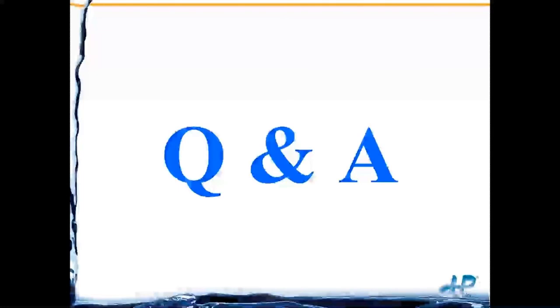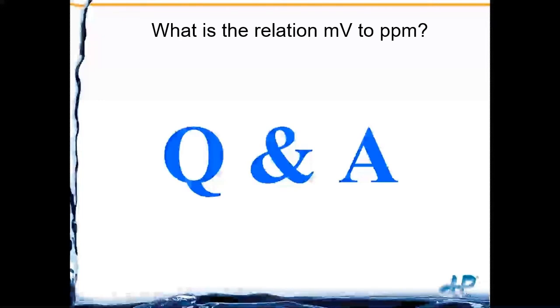Process analyzers is an always-changing world. If I don't know an answer I'll be honest, but I'll always find the answer and get it to you within the next week. First question: what is the relation of millivolts to PPM? That depends on the chemical you're referencing. For chlorine, an ORP value of about 800-825 millivolts would be equivalent to about four to five PPM. There are value charts available for different chemicals.